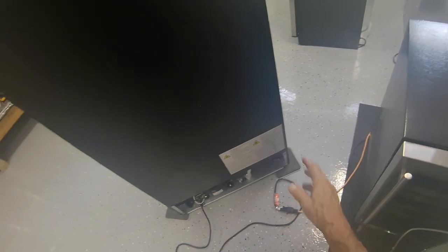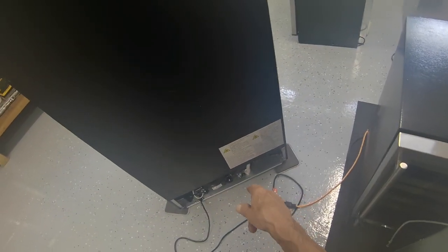So that's another thing, but the main thing we're going to do right now is, since this is a R600a unit, we don't have to use a recovery system. We can just vent this out right into the air. So I'm going to open up the garage door, shut it off, and release whatever refrigerant is in there. We'll pull a vacuum on it, and then I'm going to weigh the exact amount of gas in.